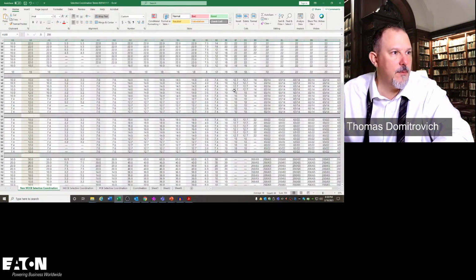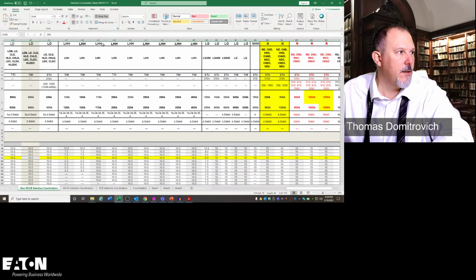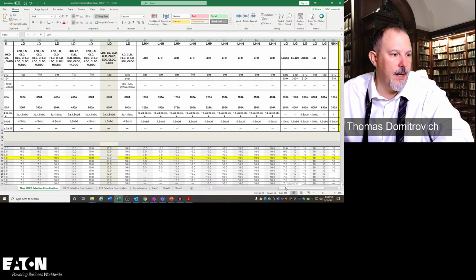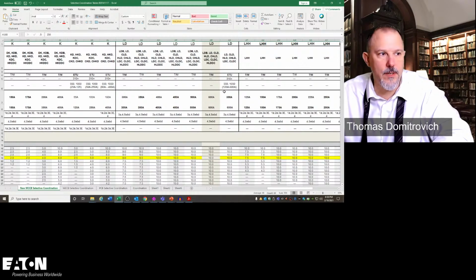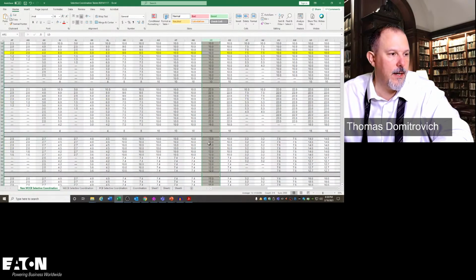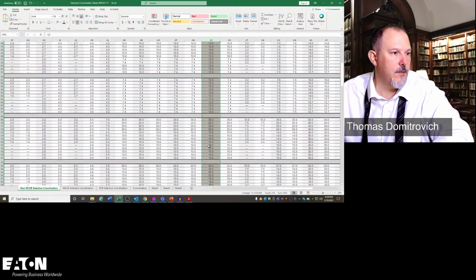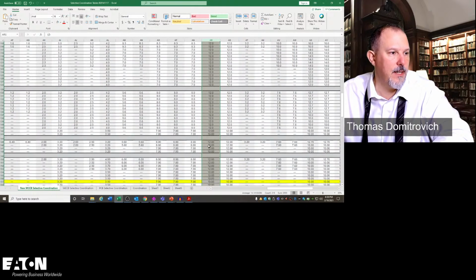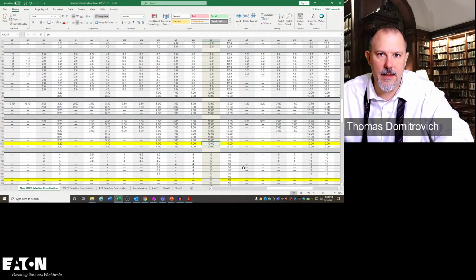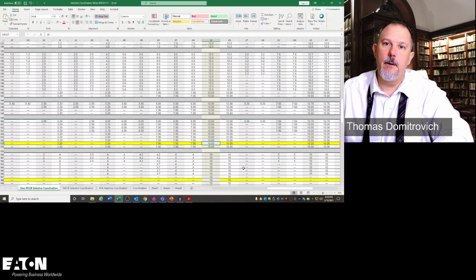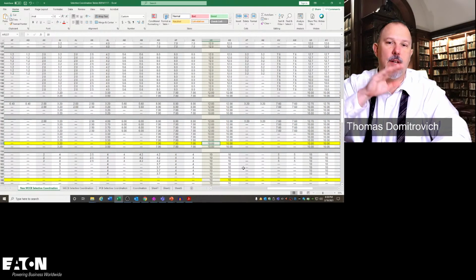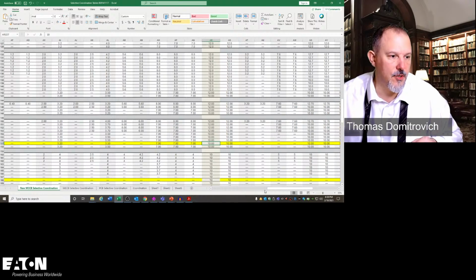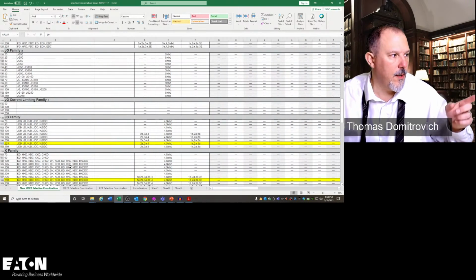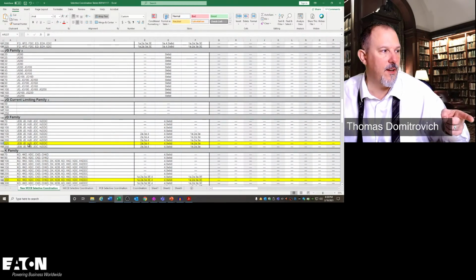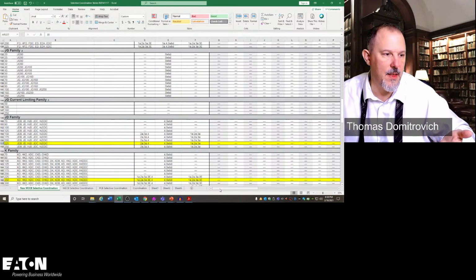If I go to the LD breaker up above, an LG, LD, and I believe it was a 600 amp? Yeah, so there it is there. If I go down to my LD, which should be highlighted right here, 10,000 amps. I selectively coordinate to 10,000 amps with that breaker. I'm good to go because I've tested. The downstream breaker is my JD 225. I selectively coordinate to 10,000 amps.